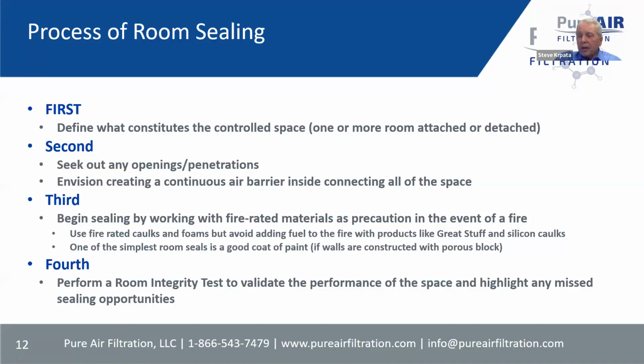The fourth thing in our process is, once we've sealed everything we think needs it -- and I'll talk about some other trickier areas in a minute -- once we think we've completed the room, we perform a room integrity test, a blower door test, to validate the space and provide data metrics on how it performs. That can be used for sizing equipment precisely, instead of just guessing with rules of thumb, which again reduces your costs.